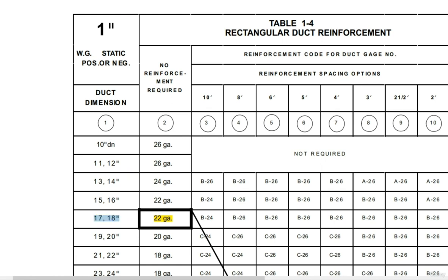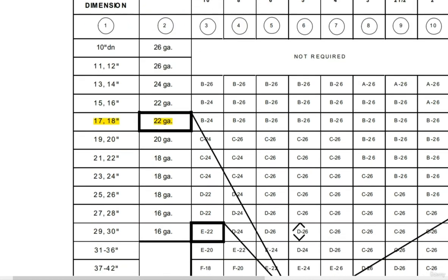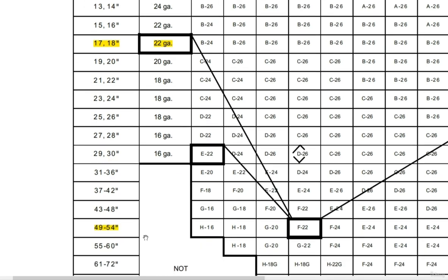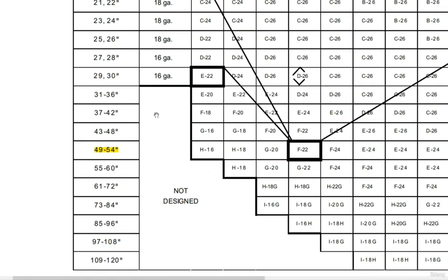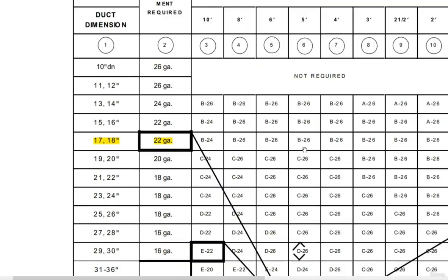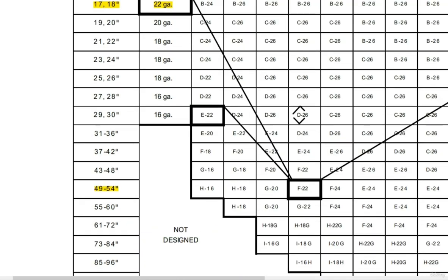For the 18-inch side I will use gauge 22 duct without reinforcement. However, for the second dimension — the width, or 54-inch duct — which falls between 49 to 54 inches, there is no value given for the duct sheet metal thickness in that slot. It is marked as 'not designed,' which means reinforcement must be installed. So I intersect that row with the column for 5-foot joint spacing, and this gives me the value F22. F22 indicates that I need to use a duct gauge of 22 with the F-type reinforcement.